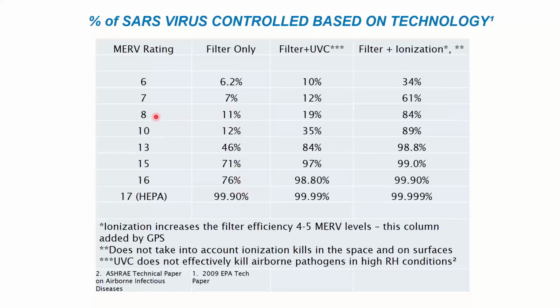A Merv 6, 8, 10 filter is doing pretty much nothing. When you get up to Merv 13, you're doing some work. It doesn't show Merv 14 here, but let's assume it's somewhere in the middle, 50-60%. That's kind of how ASHRAE is coming up with recommendations of getting Merv 13 or 14 in there, because that's going to maybe catch half of these things around that size.